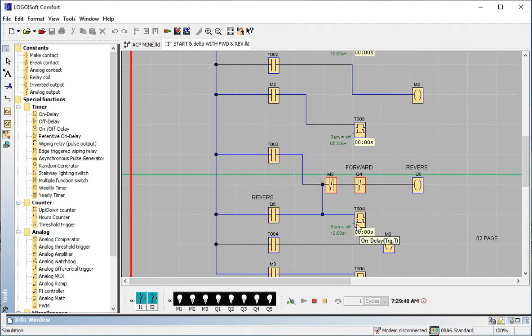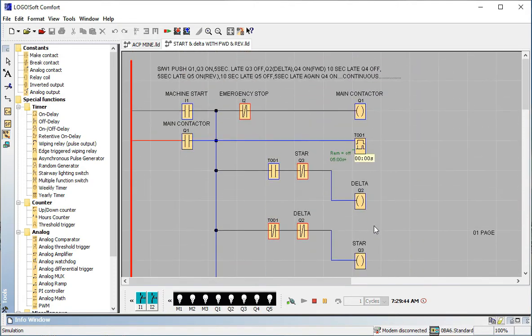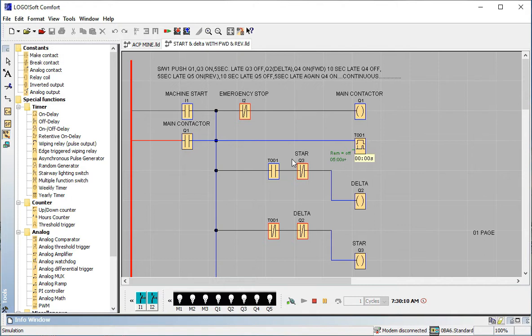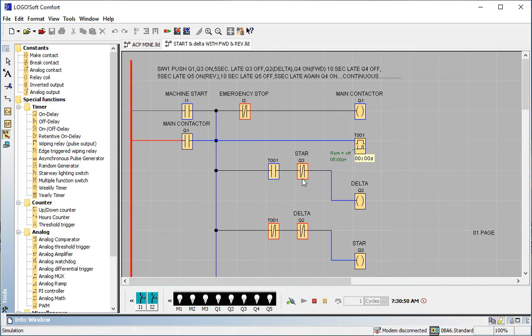After forward turns off, a five-second delay begins, then Q5 (reverse) turns on. Reverse runs continuously as a 10-second operating time, similar to forward. After 10 seconds, Q5 turns off, then five seconds later Q4 turns on again with delta. Delta plus Q4 and Q5 are both off for five seconds; after those five seconds, Q4 comes on again. This is the acceleration and deceleration delay — forcing the motor to the opposite direction instantly is very dangerous.